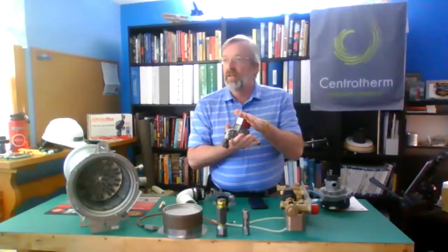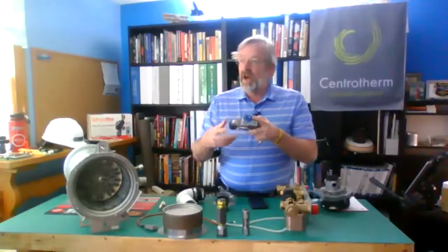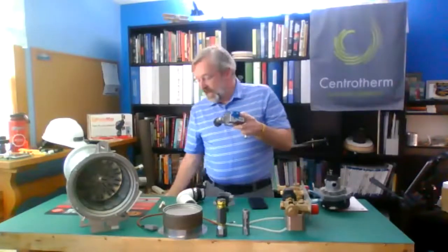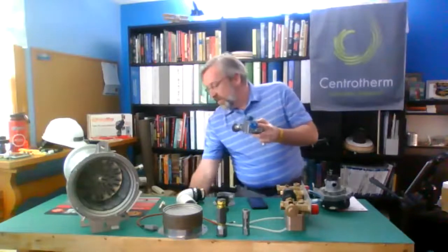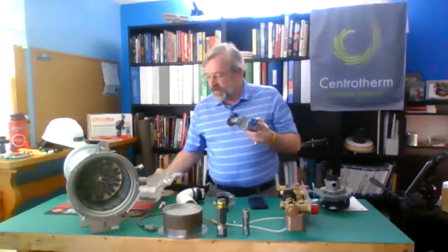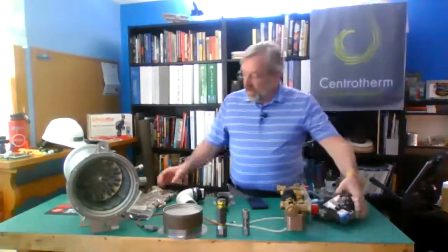And so generally, solenoid on the top, let's check that. Easy way to test is put your hand on it, okay? Do I feel it opening? If you don't feel it opening, I got a switch right here. There's an on-off switch actually on there, so you certainly can make sure that that's on. On occasion, we have had them where they're actually turned off. That's always sort of a problematic type of scenario. So make sure you turn it on. And they ship from the factory in the off position.